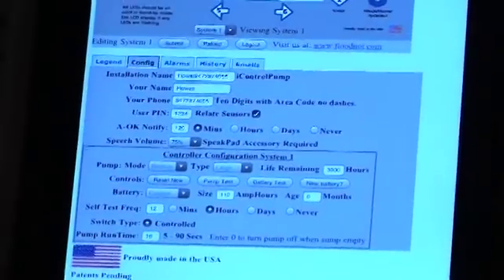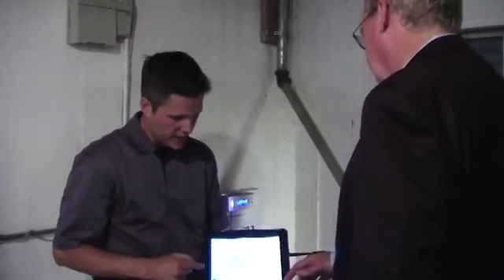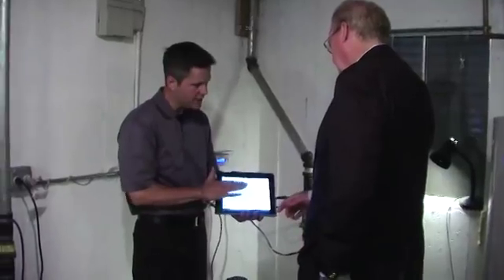The next tab is Configuration. We could turn this sideways to make it a little bigger. Configuration tells us how this system in particular is set up — for example, pump run time is at 10 seconds, it'll self-test every 12 hours, and the name is Howell. We'll white out your phone number there.